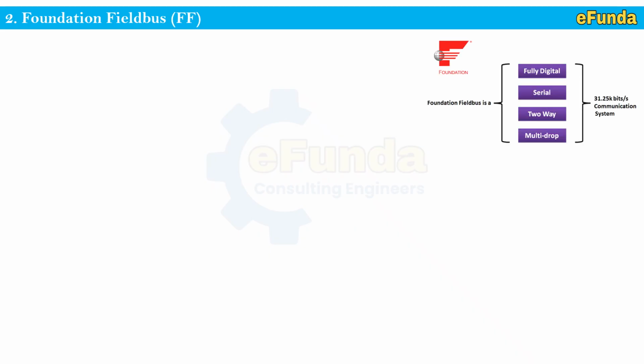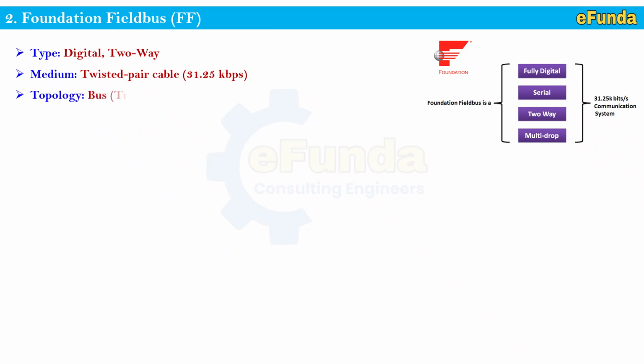Second, Foundation Fieldbus, that is FF. One can refer to the picture where Foundation Fieldbus is typically a fully digital serial two-way communication, multi-drop, 31.25 kilobits per second communication system. We'll see one by one. Type: digital two-way communication. Medium: twisted pair cable, 31.25 kilobits per second. Topology: bus, that is a trunk and a spur. Power: can carry power and a signal on the same wire. Intrinsically safe type.